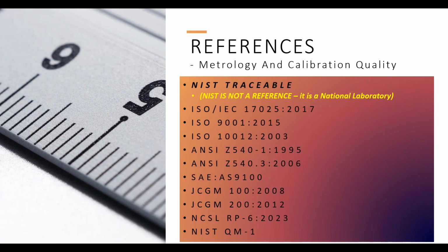They have to come in, verify our technicians are doing things correctly, verify our quality systems operating. And then we have to do intercomparisons with other laboratories in our same scope of service. So all of our work that we do gets compared against Fluke or a NASA calibration lab or just other labs. And we have to pass those proficiency tests to maintain our accreditation. Of course, ISO 9001, your general quality management system. ISO 10012 is your basic metrology calibration program.